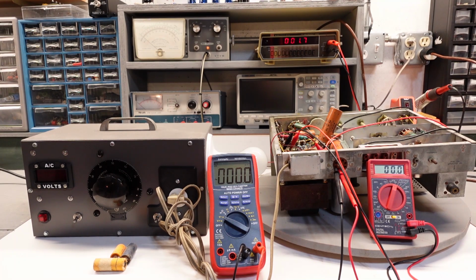So what I like to do — obviously the most simple thing is just check the resistance on the primary and all the secondary windings. That would be a basic check, but I like to take it a step further and actually put AC voltage on the primary and measure the voltages on the secondary, with no load.